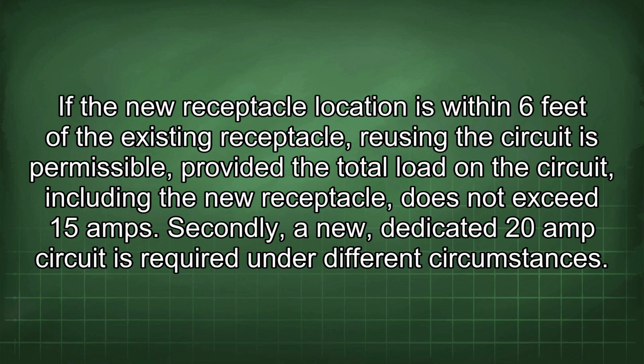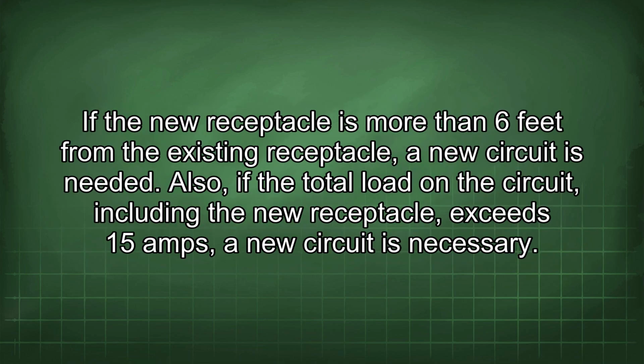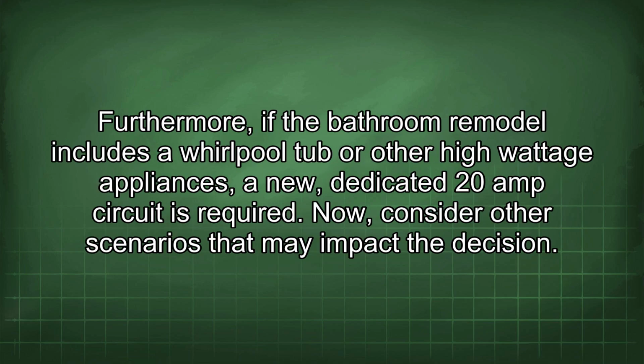Secondly, a new, dedicated 20-amp circuit is required under different circumstances. If the new receptacle is more than 6 feet from the existing receptacle, a new circuit is needed. Also, if the total load in the circuit, including the new receptacle, exceeds 15 amps, a new circuit is necessary. Furthermore, if the bathroom remodel includes a whirlpool tub or other high-wattage appliances, a new, dedicated 20-amp circuit is required.